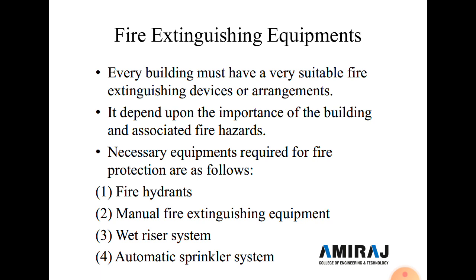And the fourth point is the automatic sprinkler system. It is used in industries like textile mills and paper mills, and also in malls and shopping centers. In this system, a network of pipes of 20 diameter is fixed on the ceiling of the room, and sprinkler heads are fixed to the pipe at regular intervals. A fusible plug is provided in each sprinkler head, and the sprinkler heads get supply from the pipe. At the time of fire the fusible plug starts melting due to the rise in temperature, and water comes out forcefully from the sprinkler head, making it easy to control the fire by sprinkling water on it.